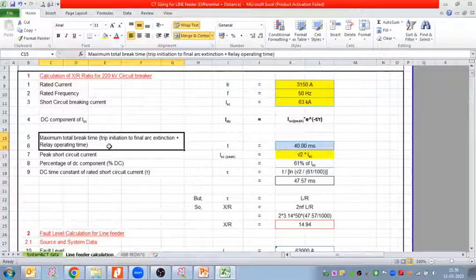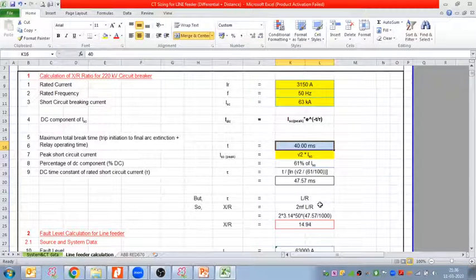Maximum total break time is trip initiation to final arc extinction, plus a relay operating time. So we can see what relay we are taking and what its operating time is, plus the circuit breaker opening, breaking time. We can add both the circuit breaker opening time and the relay operating time. For that you need to refer to the GTP or nameplate of the circuit breaker you are taking. From that you will get the circuit breaker opening or breaking time when the fault is happening. So this T would be your circuit breaker opening time. Here I have not added the relay operating time, but we can add it also, so 40 plus 10.